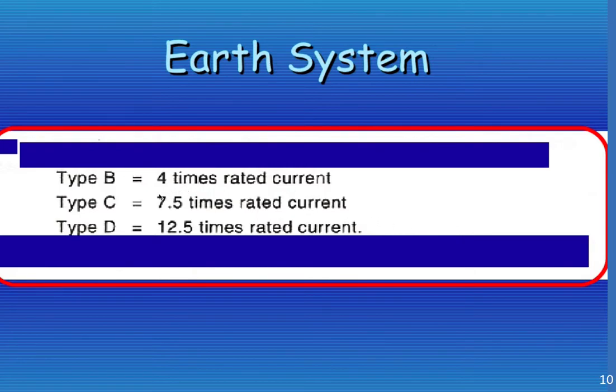So again, here's our different types of characteristic curves. There's a type B curve, a type C curve, and a type D. Type B needs to be four times rated current to trip in the appropriate amount of time. Type C needs to be seven and a half times the rated current, and type D needs to be twelve and a half times the rated current.